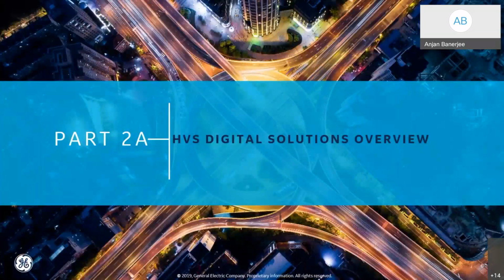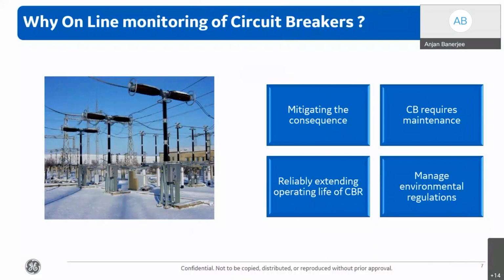Now let us turn our attention to the digital solutions that we offer for effective management of the switchgears that I explained in the previous slide. Before I mention the features of the digital solutions that we offer, let us first try to understand why we need digital solutions for online monitoring. We first take the example of the circuit breaker. We are all aware the circuit breaker is one of the most critical pieces of equipment in the power system network. Say for example, we have a fault in the equipment. Even though the protection relay has sensed the fault and given a command to the circuit breaker to operate, the circuit breaker has not been taken care of properly and it has failed to operate.